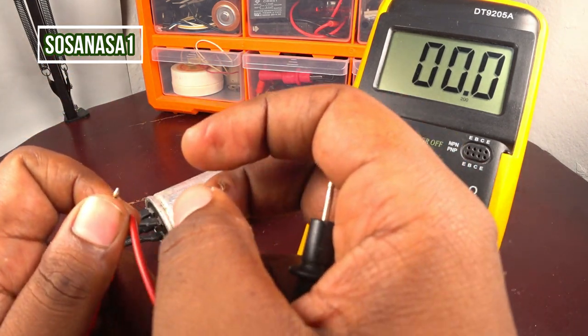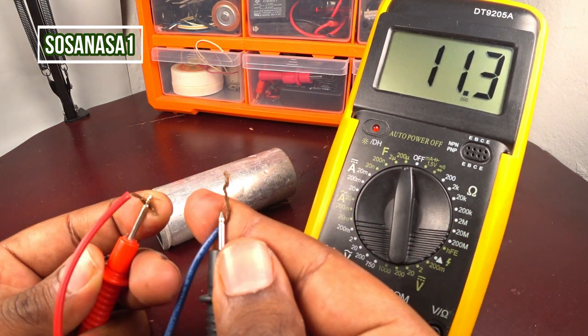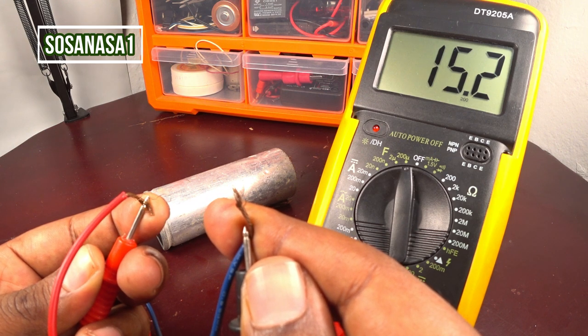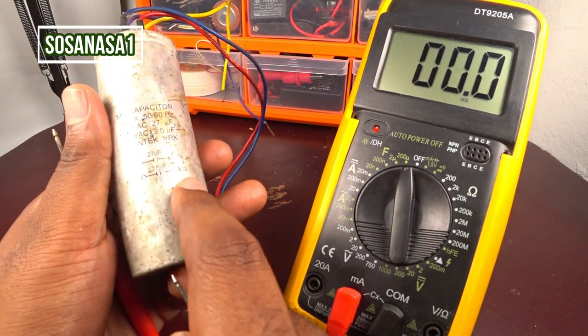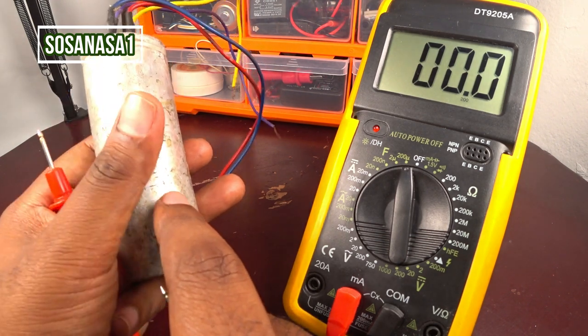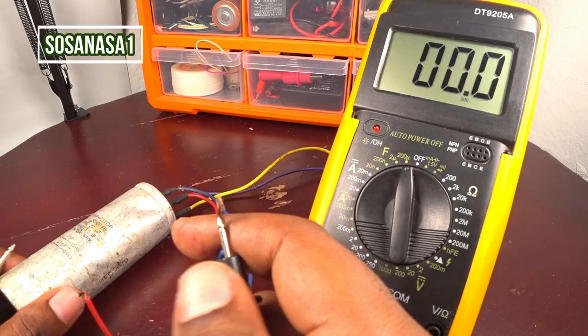Let's touch the red tip to the red cable and the blue cable, and watch the multimeter screen. This capacitor reads 15.2 microfarads. On the capacitor label, the blue with the red cable combination is rated at 13.5 microfarads, and the multimeter shows 15.2 microfarads. It means this capacitor is in good condition.